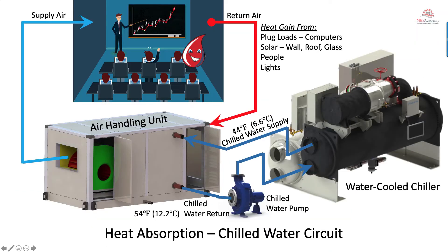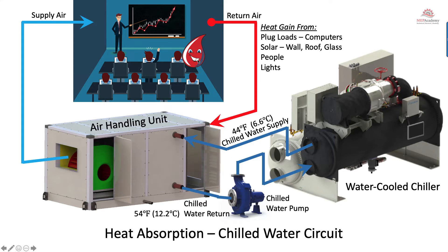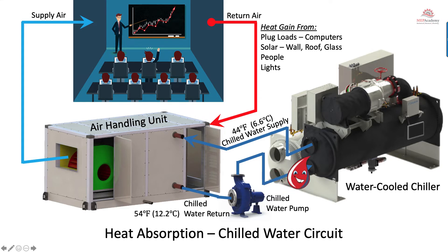To recap: heat comes from people, plug loads like computers or any equipment generating heat, lighting, and solar — whether through windows or conducted through walls from outside air. That heat is generated in the space and we want to remove it. It's taken through the return air duct into the air handler, passed into the chilled water system, and from there taken into the chiller.